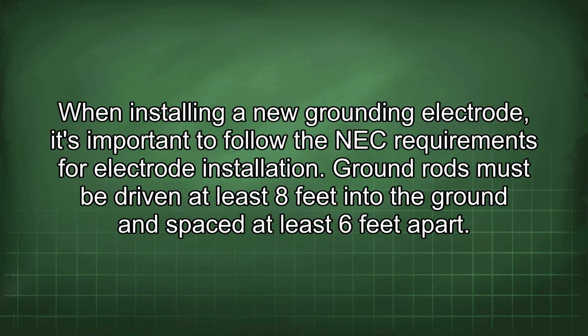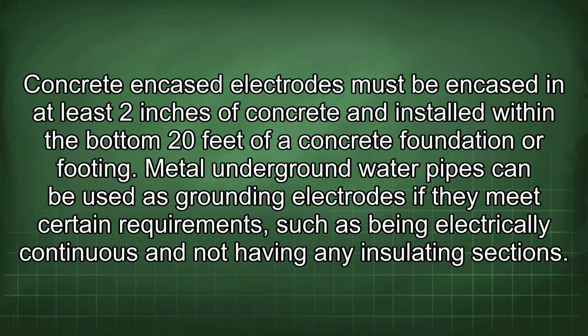When installing a new grounding electrode, it's important to follow the NEC requirements for electrode installation. Ground rods must be driven at least 8 feet into the ground and spaced at least 6 feet apart. Concrete encased electrodes must be encased in at least 2 inches of concrete and installed within the bottom 20 feet of a concrete foundation or footing. Metal underground water pipes can be used as grounding electrodes if they meet certain requirements, such as being electrically continuous and not having any insulating sections.